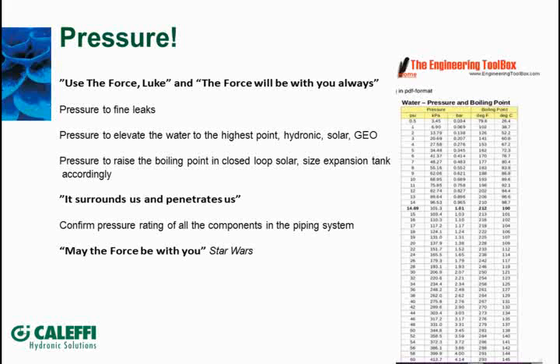So that's another reason for doing that. Another reason for increasing the pressure on the system: if you've got a problematic air elimination problem, sometimes just putting another 5 or 6 pounds of static fill pressure on it can help. What it'll do is squeeze those bubbles, and it'll help them come together and move back to the point where you can eliminate them. Some guys that are having problems with a multi-story building getting the air out of it will sometimes go back and bump that fill pressure up a couple pounds until they get all the air out of it, and then set it back down to what they want it to be at.